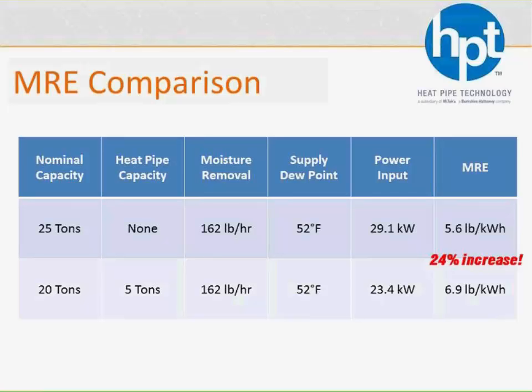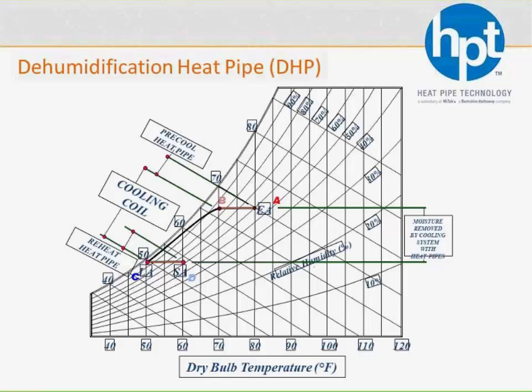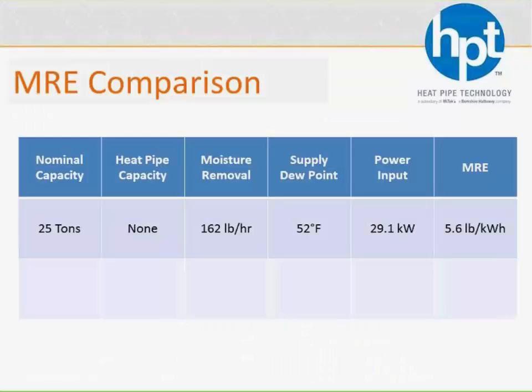Now, another cool thing you can do is not just take the same DOAS unit and get the same total capacity, but let's say we want to dry out the air even further. Let's say that that 25-ton system without the wraparound heat pipe on it can only get down to that 52-degree dew point. Well, now you add a wraparound heat pipe to it. We're going to do some pre-cooling, so that same cooling coil is going to do less sensible cooling, more latent cooling, and drive down that dew point even further.